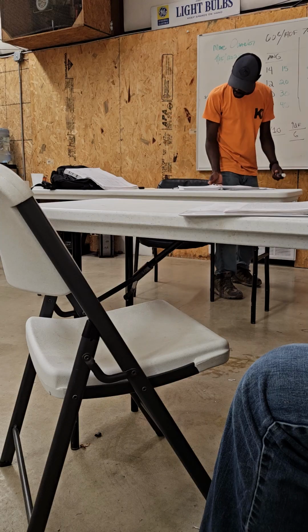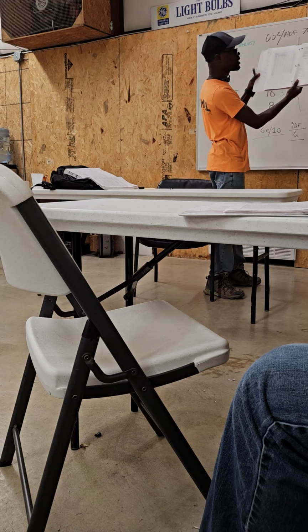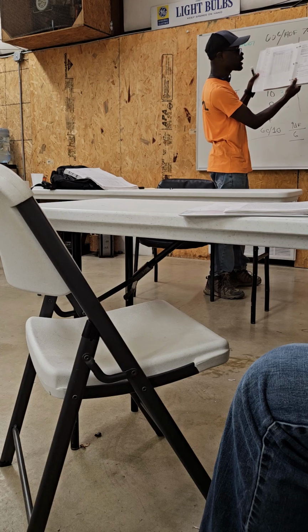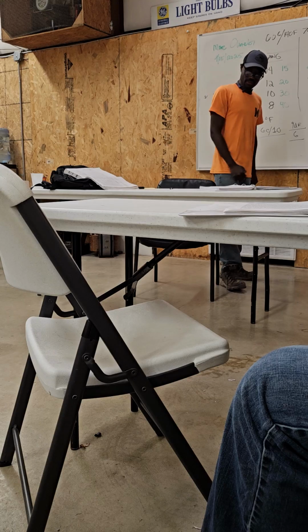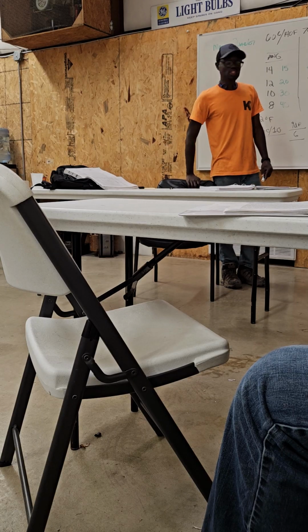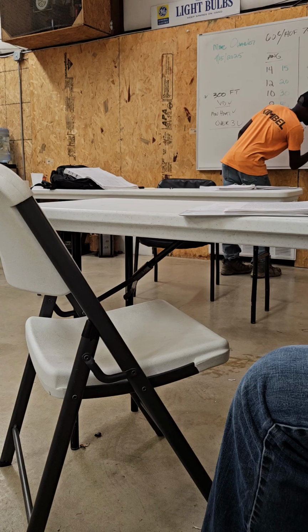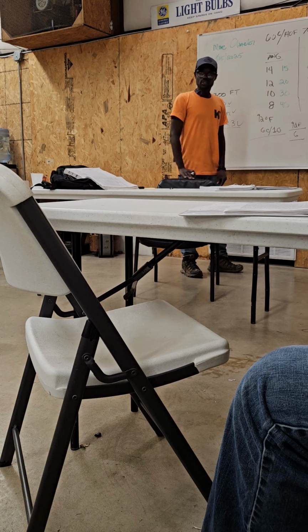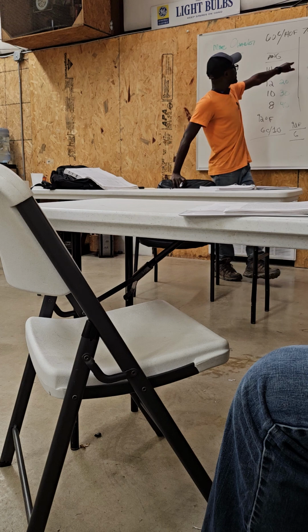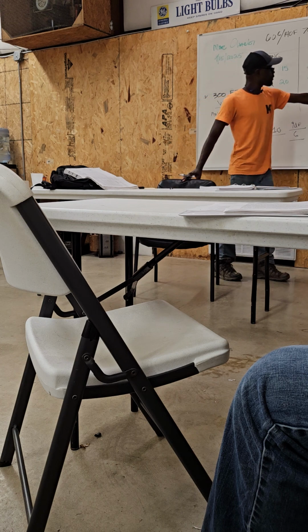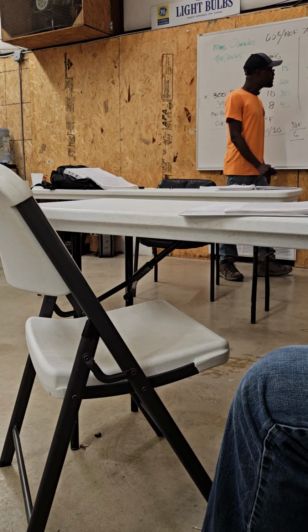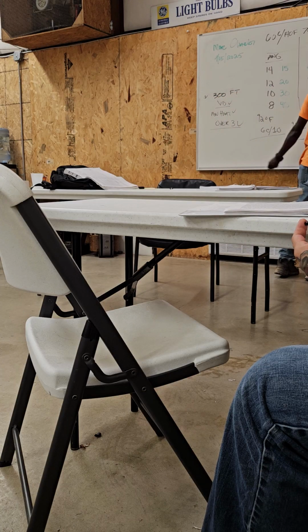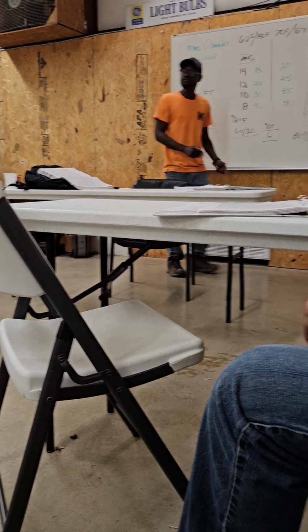When you go to this table here on page 89, it's going to tell you the number of current carrying conductors. It says if I have between 4 to 6 conductors, that's how much of my amperage is good now. It's only 80%. So all of a sudden, my number 8, over here, that's good for 55 amp. Read on that column. Now it's only good for 80%. So the maximum amp I can carry is 80% of 55, that would be 44 amp.